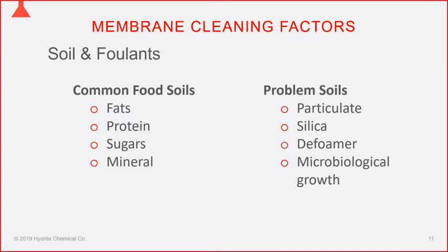There are other sources of soil that can cause major problems. Particulate soils — for example, a worn pump grinding metal particles into your system — are problematic. A water supply with clay, silica, or sand can deposit insoluble particles on your membranes. Silica can come from your water supply or from defoamers, which often have hydrophobic silica homogenized into them. Removing silica requires something like hydrofluoric acid, but that would also destroy your membranes, so once silica is in, the only course is to change membranes.